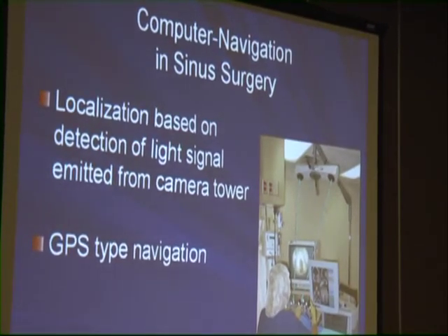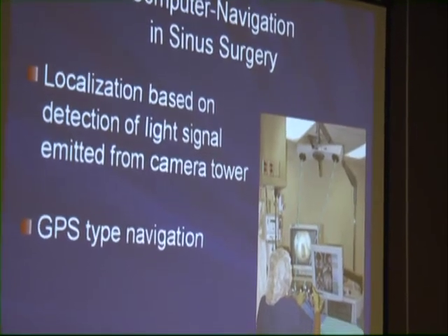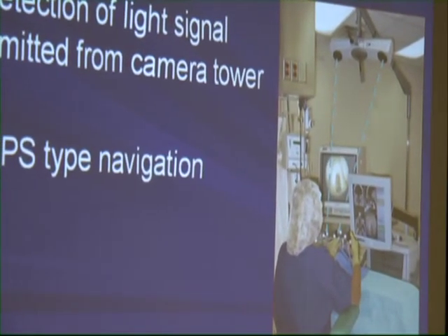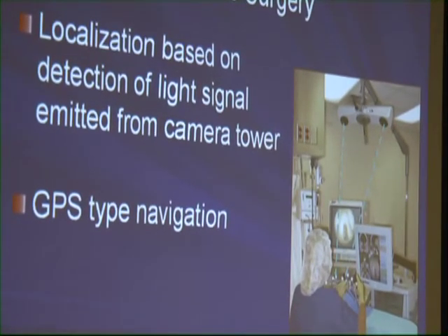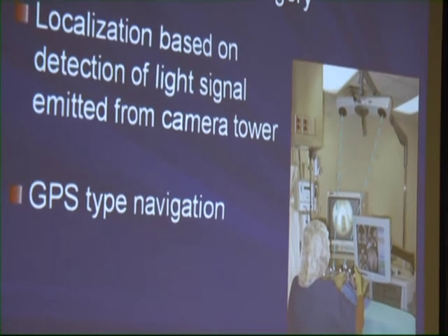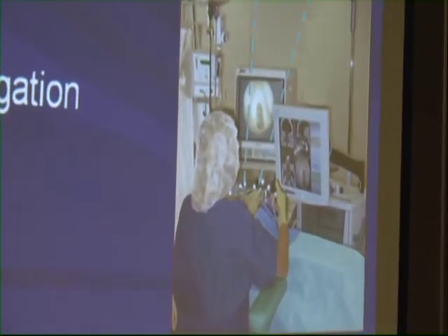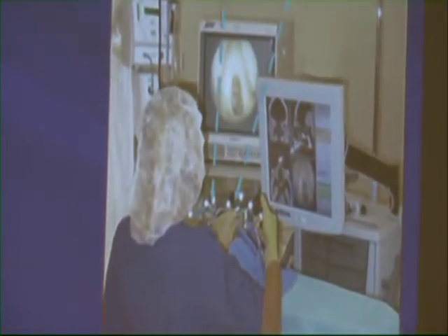Tracking technologies perform very similarly to satellite navigation for geographic positioning by precisely and dynamically tracking the signals from the trackers on the surgical instrument and also on the patient reference device. As data from the tracking method registers to the navigation system computer, it is visually merged with the pre-op CT scan on the system monitor in real time.